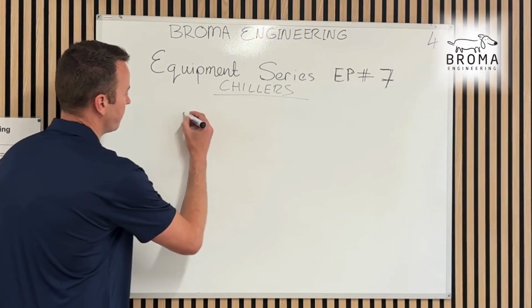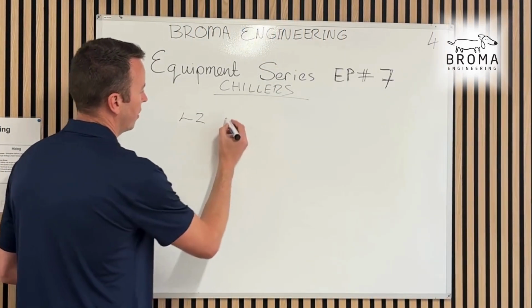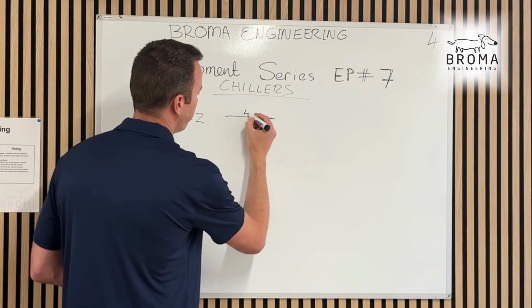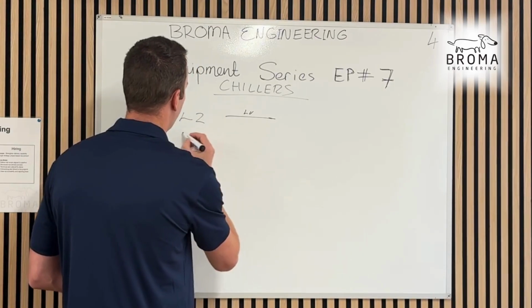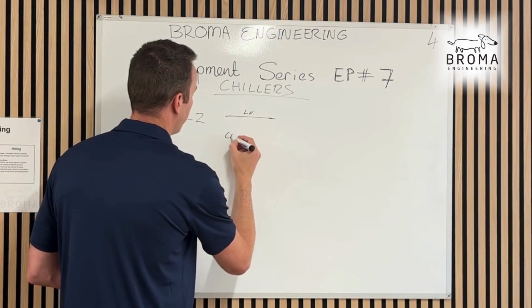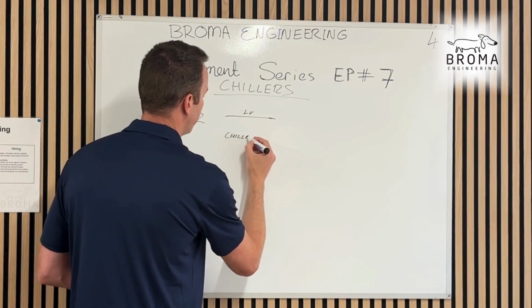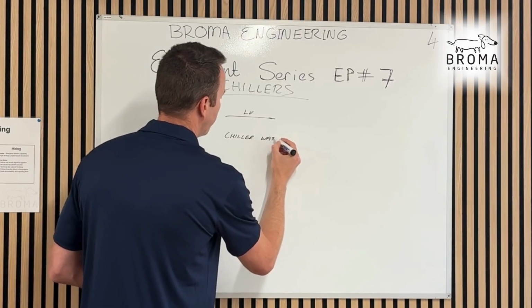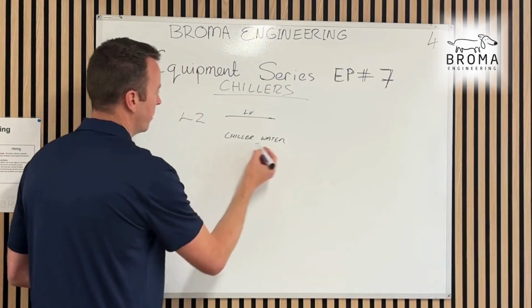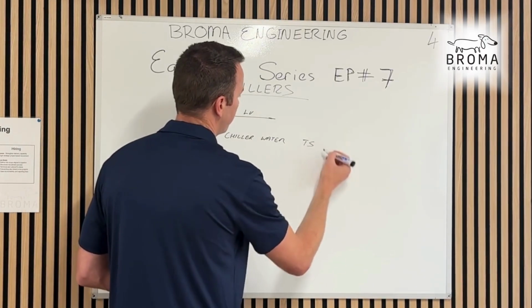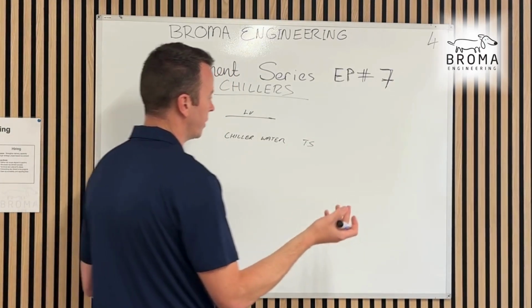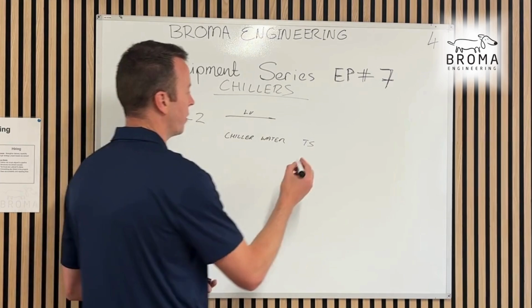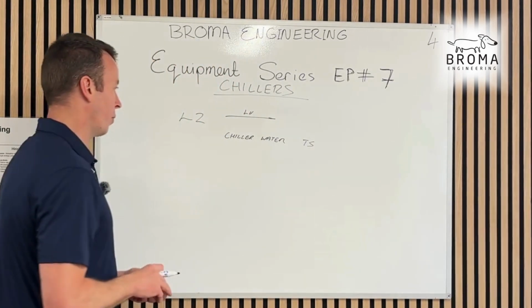Okay, so level 2. We have it set in place. We're getting our LV cable, there might be two of them. Our chill water pipework has to be connected, so this has to be designed. There has to be a technical submittal in for it, and it has to be approved. Of course the chiller as well, but if it's OFCI, usually the technical submittal will already be approved by the time you get there. But make sure it is.